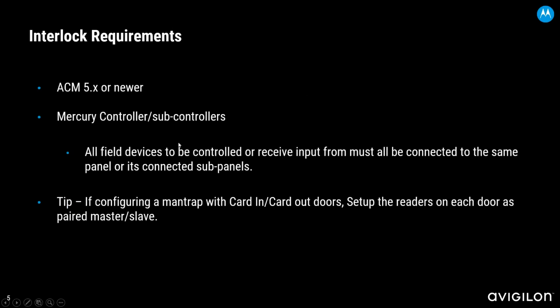So interlock requirements, I'm going to say any newer version of ACM is going to support interlocks. You're going to need to use Mercury controllers and subcontrollers. So the interlock function is not supported on the HID controller line. And just a reminder, the field devices that you're going to control or receive input from all need to be connected to the same panel.